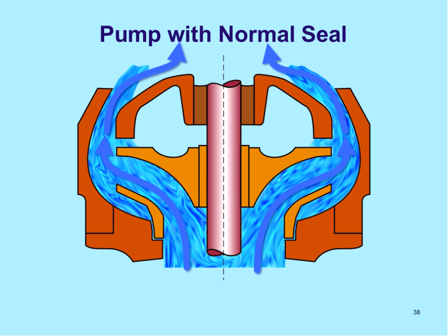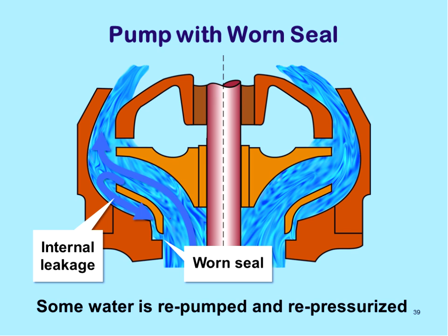So here's an example of a pump seal. This is looking at a stage, so this would be one section of a pump. This is the impeller that spins around. The rest of this is stationary. So the water's moving up through here, and we have this seal right here. Sometimes this will wear, and when it wears, all of a sudden we get this big gap here, and so the water will come back around. So you get leakage. We're spending the energy to pressurize it, but then it's leaking around. So that reduces the efficiency.